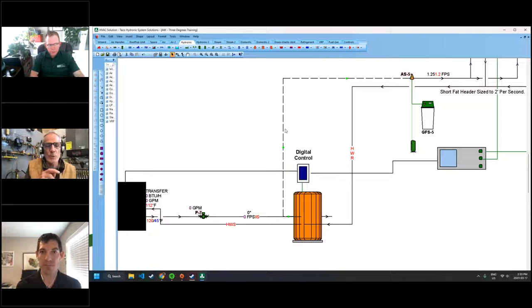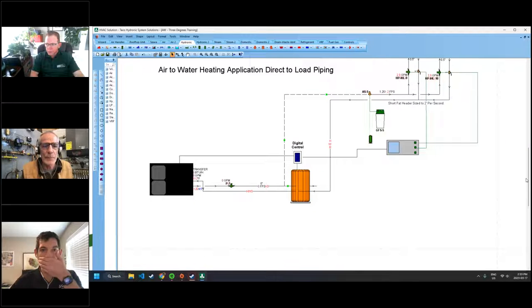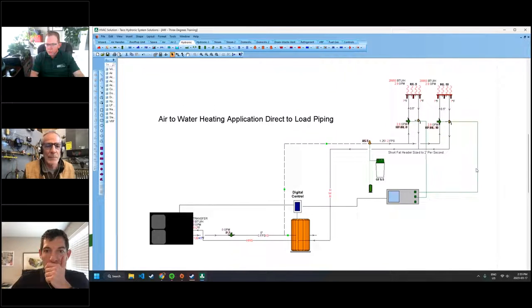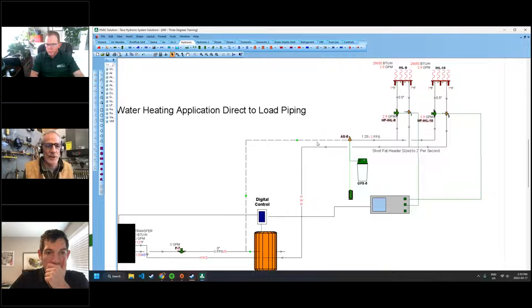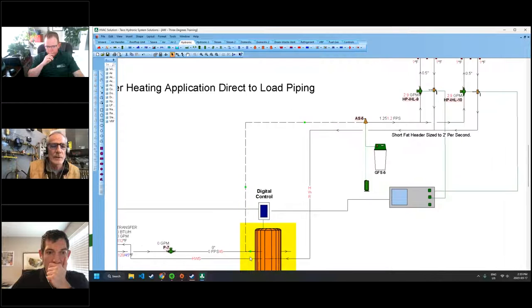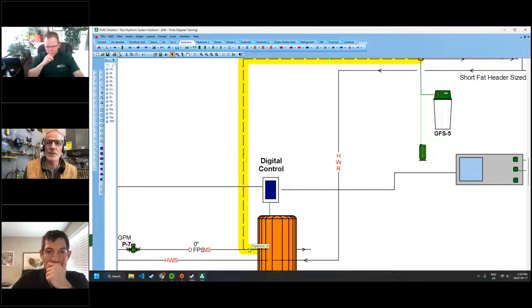What a 2 pipe does is you come out of the boiler, out of the heat pump, and you go directly to load. Because if you look at the pipe from the heat pump to the tank, on the bottom, highlight that. That's your most precious water. Whatever the heat pump did to that water, that's the most precious, and you want to use that as quickly and efficiently as possible. So you want to take that direct to the load.